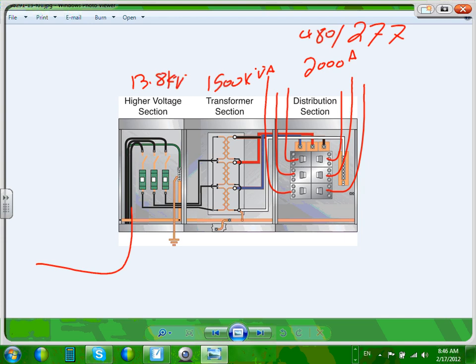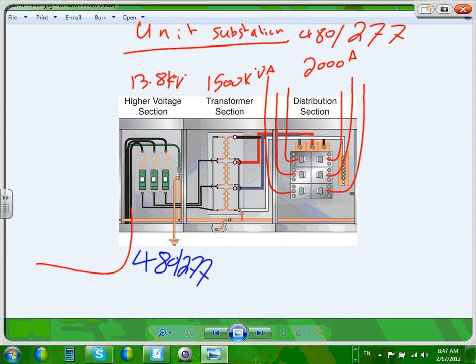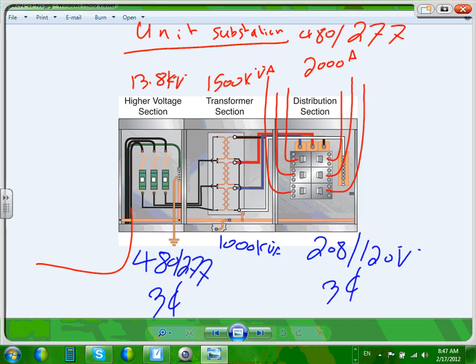Sometimes, as I said, in hospitals, you as an owner have full control over this, the whole unit substation, so-called unit substation. Let me tell you what we have done in a unit substation that you have full control over. So this is kind of utility work. If it's not utility work, what we've done is you bring a 480/277 system into a transformer, let's just say 1000 kVA, into a 208/120 volt system, all three phase, obviously, all three phase.